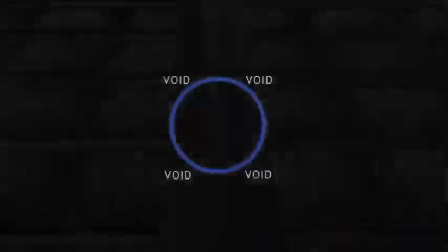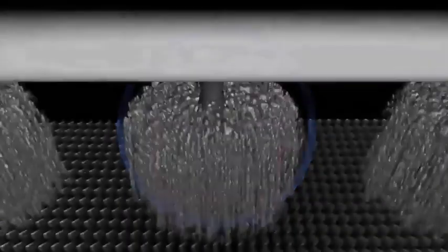Almost all cooling tower nozzles spray in a round or circular pattern, and that's a problem. A circle won't cover a square unless it's really oversized. So to compensate, companies design in an overlap in the spray pattern to eliminate these voids. So why does this matter?